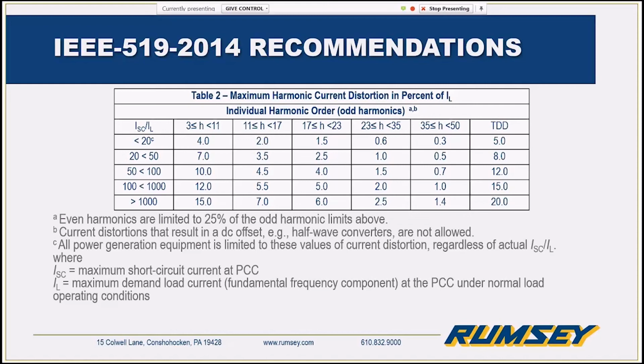And this is something that we can help you to do. I'm sure Rumsey can help. We can all take a look at any information you have to help try to find what band you fall into. But active harmonic filters are designed to meet that 5% spec. And anytime you start to look outside of 8%, an active filter would probably be more expensive, because it would be providing more correction than what you're needed as per the utility requirements.